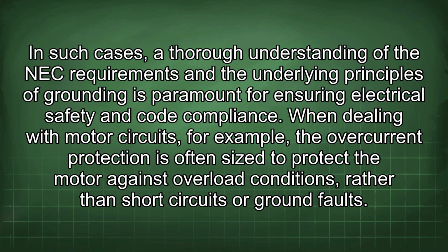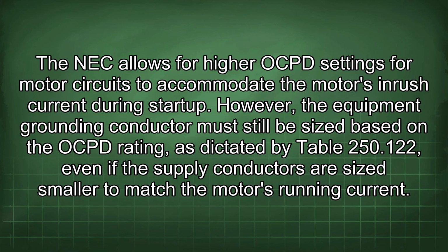When dealing with motor circuits, for example, the overcurrent protection is often sized to protect the motor against overload conditions rather than short circuits or ground faults. The NEC allows for higher OCPD settings for motor circuits to accommodate the motor's inrush current during startup.